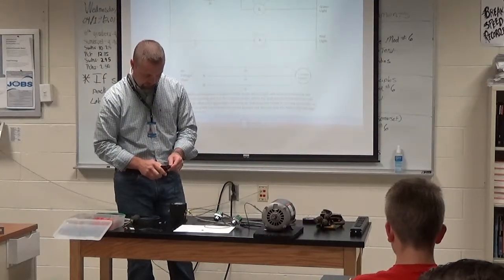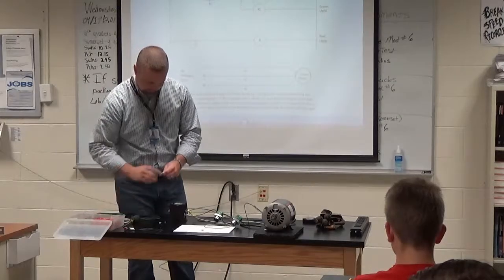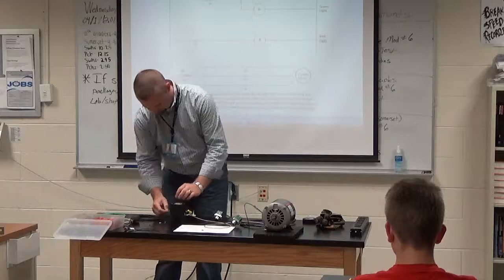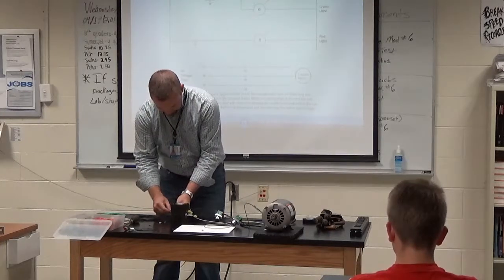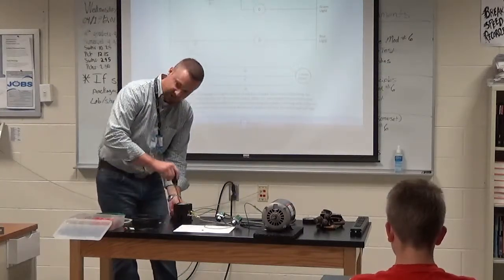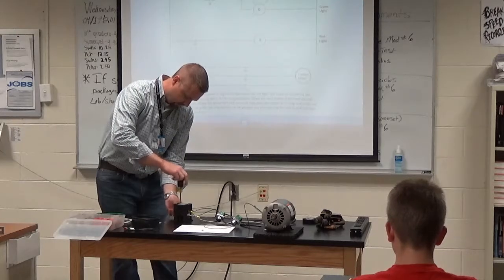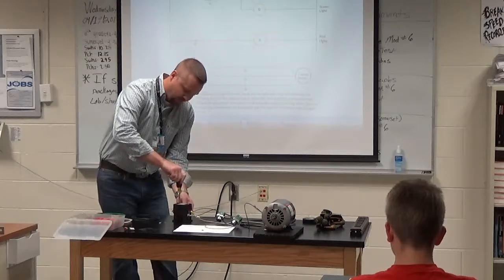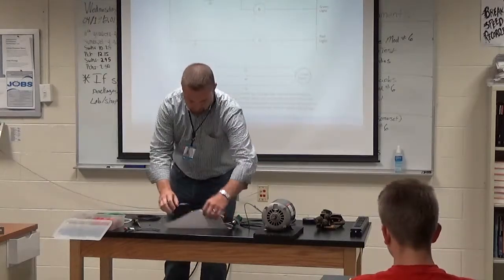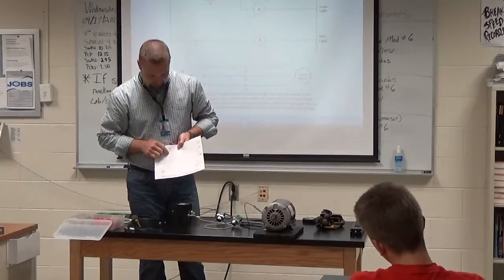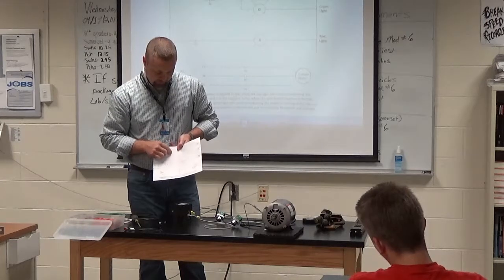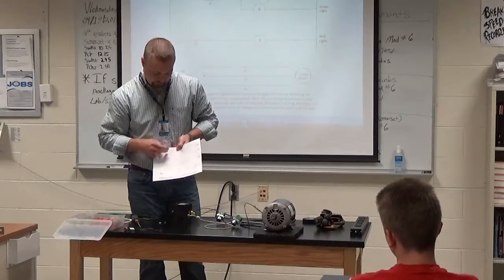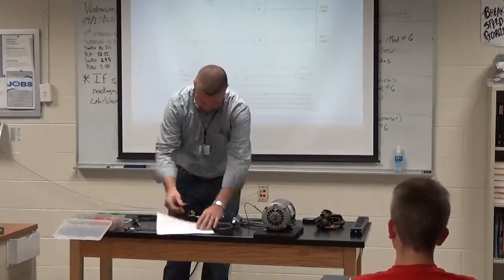Okay, now my next step is I'm coming out of my auxiliary contact block on an open and going to the opposite side of which button? Your stop button. Opposite side of the start, right? Create that holding circuit around that start button. Because basically you're creating a path, a detour around that start button to be able to take your finger off that and that motor continue to run. Okay?